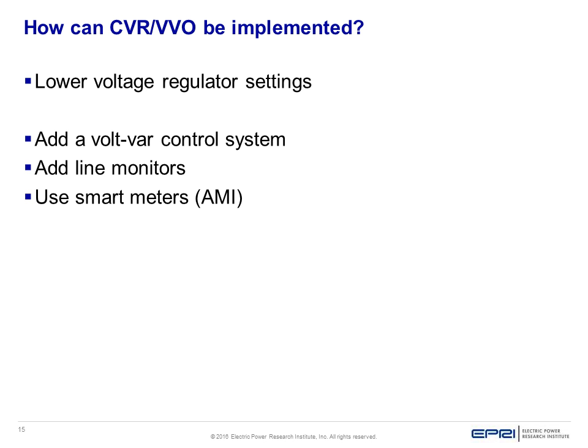But then there are more advanced ways of controlling voltage. One is that there are several commercial VVO control systems - they control capacitors and voltage regulators, and may have various types of monitoring and system models to keep track of everything and more optimally control voltage and VAR flows, keeping the voltage as low as possible to as many customers as possible without giving some customers under-voltages. Some of those systems also involve special meters placed at key points on the distribution system where voltage is most likely to go low, so the idea is to keep an eye on that and keep pushing voltage down without letting it go too low.